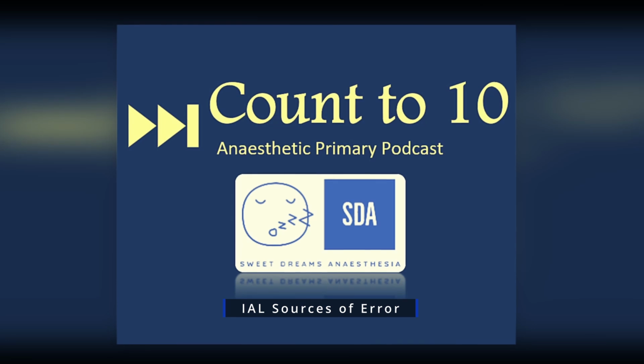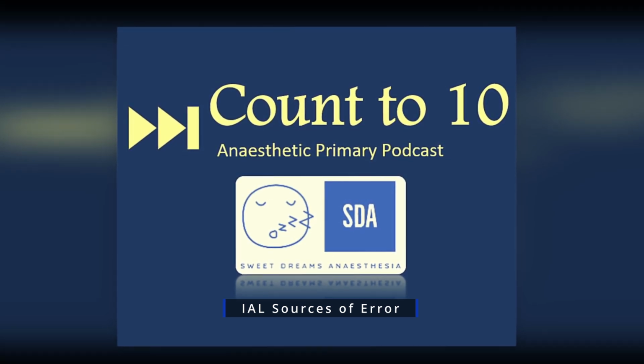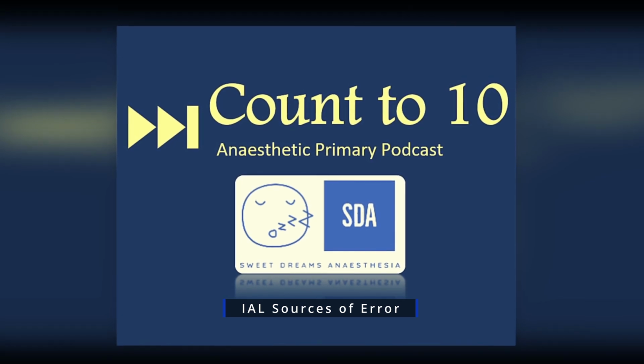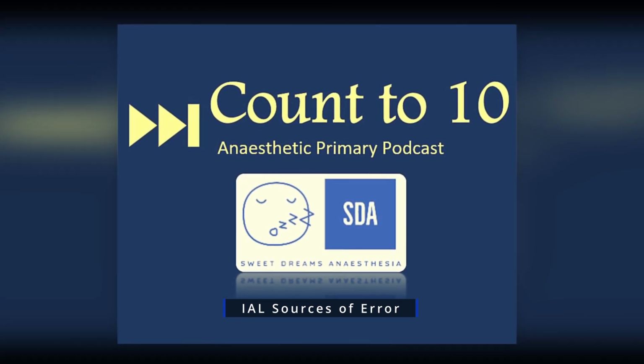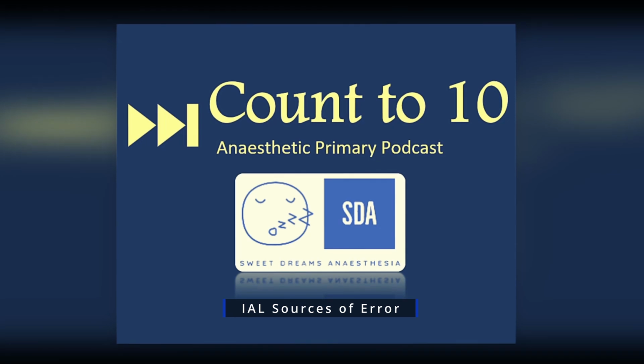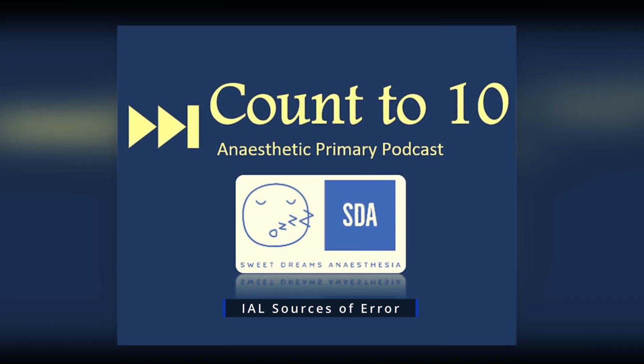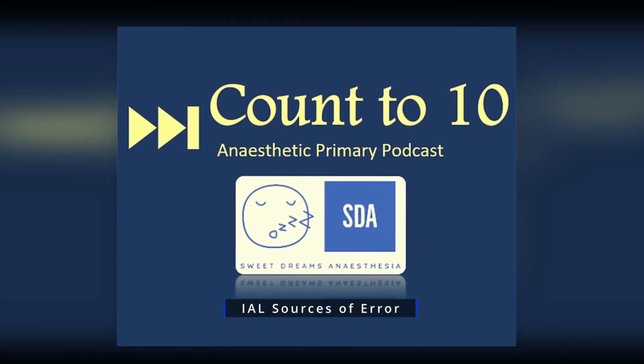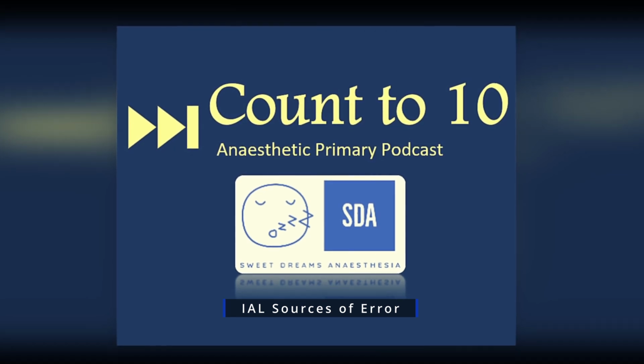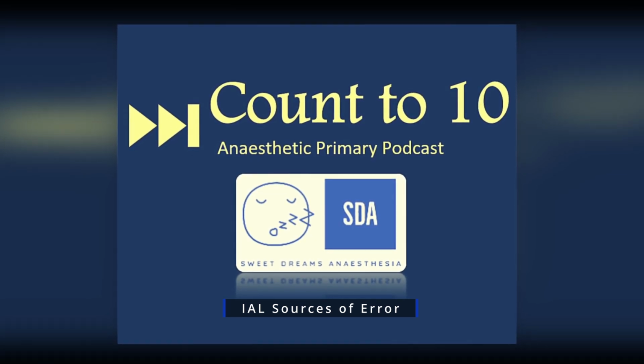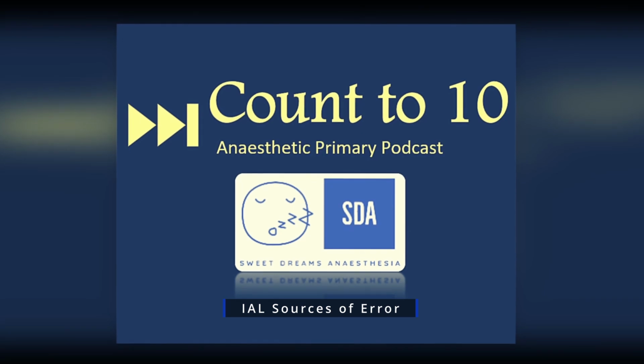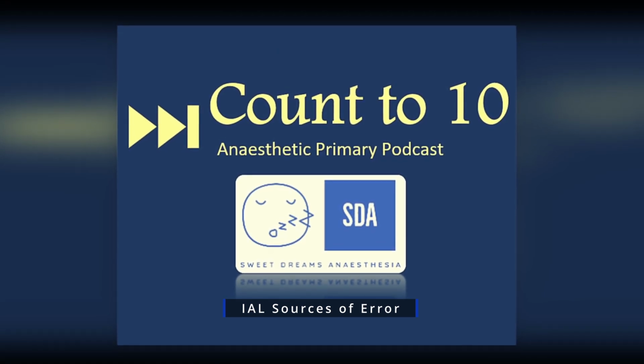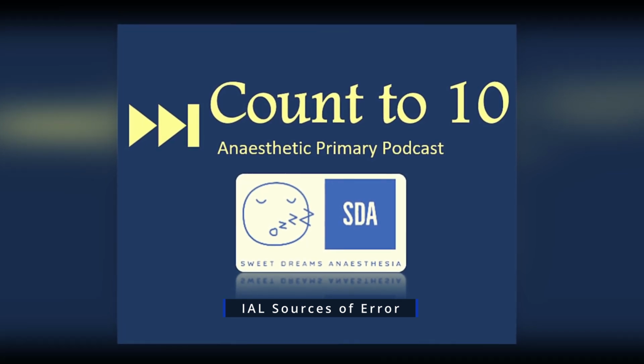In extreme cases, heart rate can be 180 to 200 beats per minute. This is 3 to 3.5 Hz. So what that means is that the arterial system's natural frequency should be well above that. And we say the minimum it should be above is 8 to 10 times the natural frequency of arterial pulsations. Therefore, the minimum natural frequency of an arterial system should be at least 24 to 30 Hz. Current arterial systems actually have a natural frequency well above that, into the hundreds to 200 Hz range.